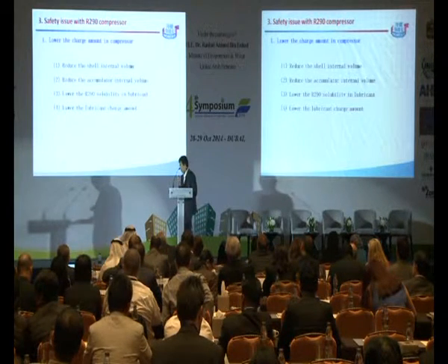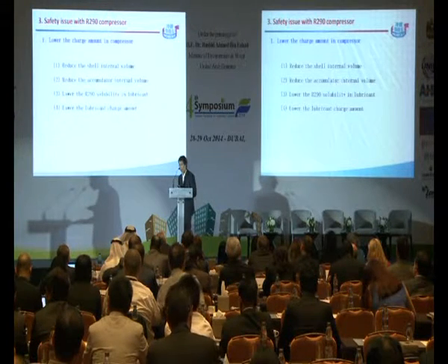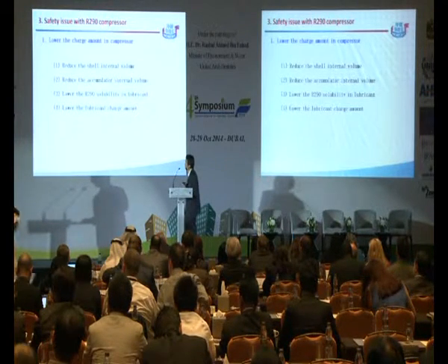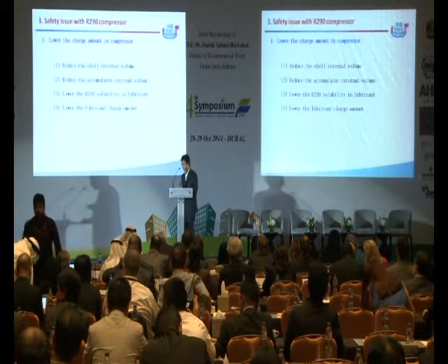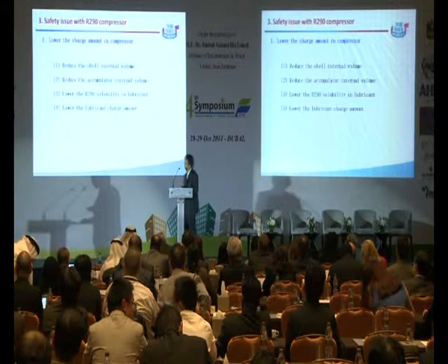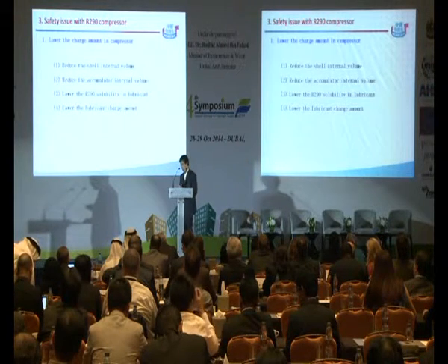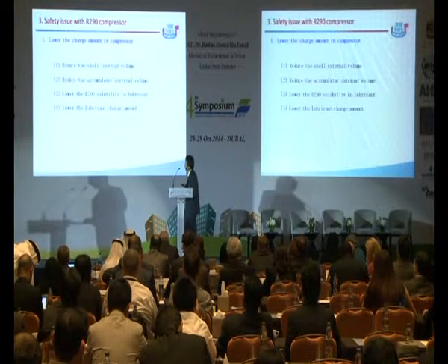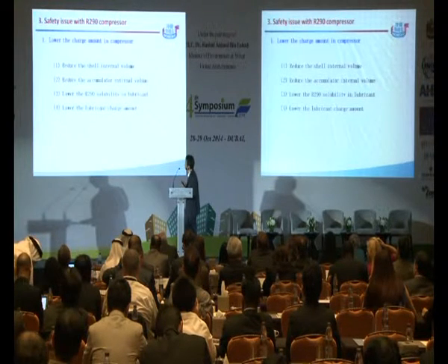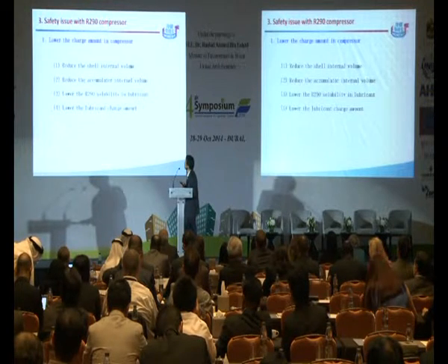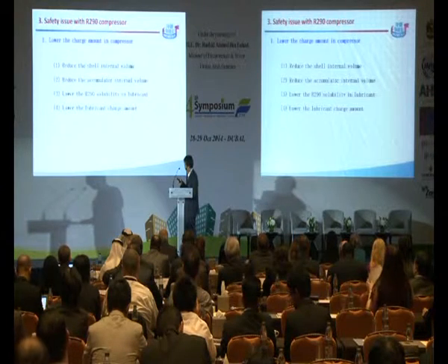For the R290 compressor, another important issue is safety. Many international standards have set the charge limit for flammable refrigerant for safety reasons. So for the R290 compressor, an important method to ensure safety is to reduce the charge amount in the compressor. Mainly we have these methods.